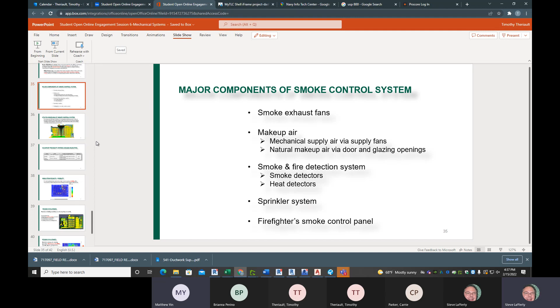And then also you will need a smoke and fire detection system, because that's how the smoke control system is activated. Most of the time, the smoke control system will be activated by smoke detectors. And depending on the location, it can also be activated by heat detectors. And other than that, you also need a sprinkler system, because the sprinkler system can also activate your smoke control system. Once that goes off, you have water flow being detected, and that will send a signal to the smoke control panel, which activates all the sequences of operations that are programmed into the system.